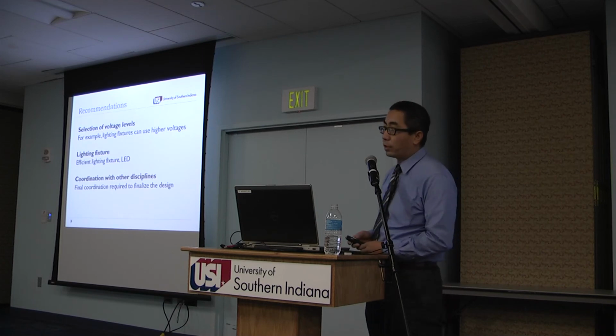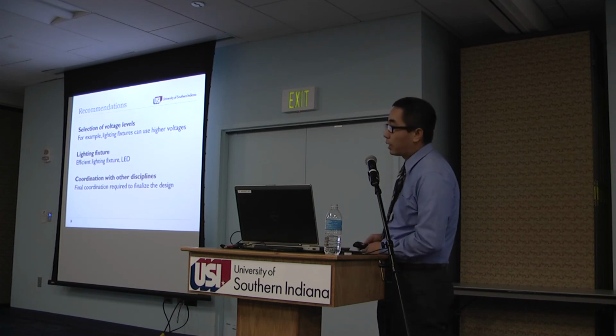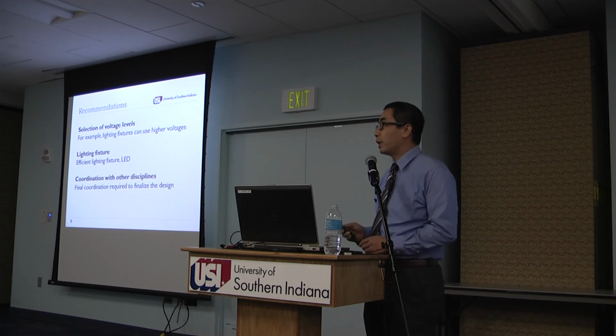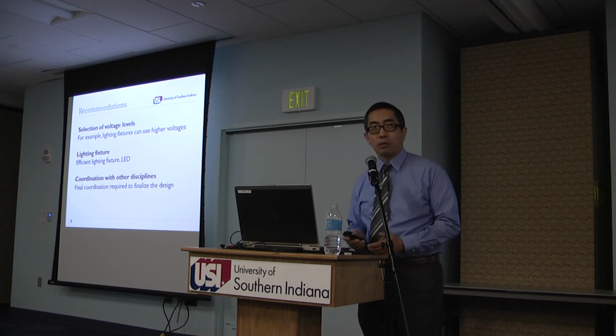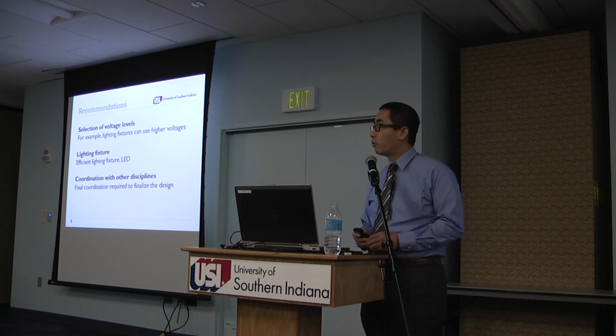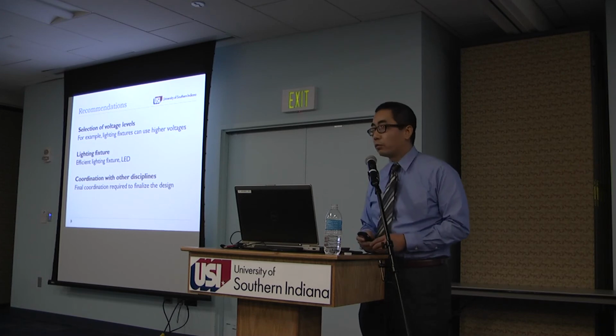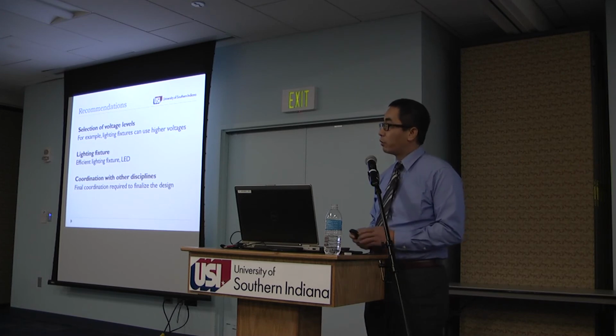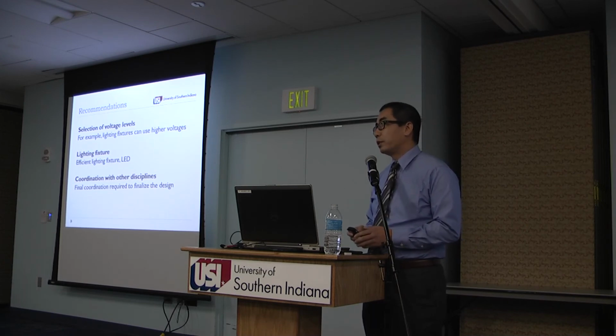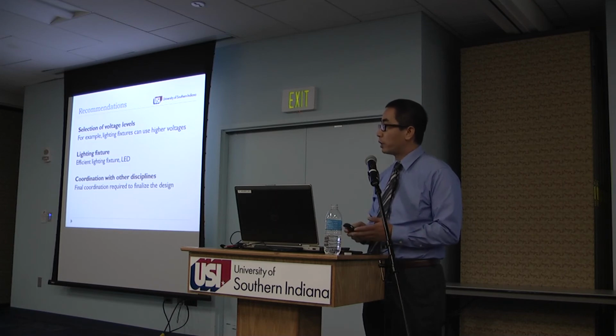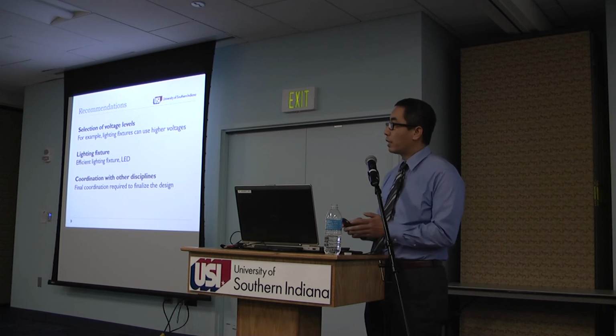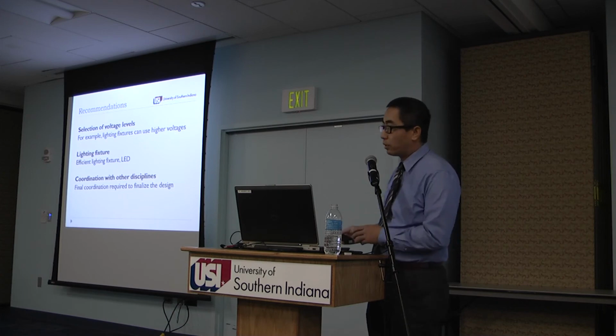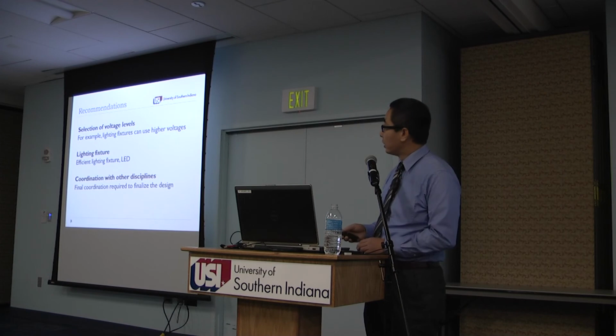And some of the recommendations: selection of the voltage. Lighting fixtures can be powered from 120 volts. They also can be powered from a higher voltage level, say 240, 277. If you use a higher voltage level, you can lower the current and make the wire smaller. But if you have too many different levels of voltage, then you have too many transformers and panels, so you have to compromise. Either you invest in the wire or put in more panels.